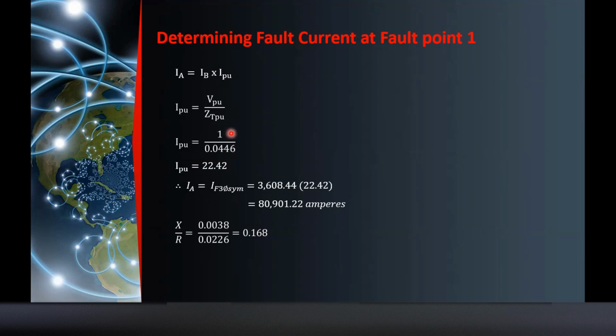Sir, bakit po naging 1? We assume that, di ba may formula tayong V per unit is... nawala ako. So IPU, sorry. So pag naging 1 yan, VA is equals to VB times V per unit. So since naka per unit yan, we assume that the actual voltage of 400 volts is the same as your 400 volts declared base. Kaya naging 1. 400 divided by 400 is 1 per unit.